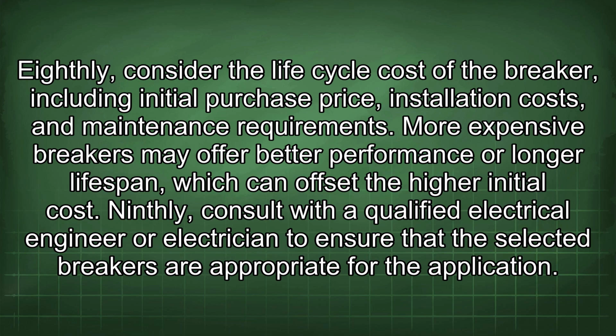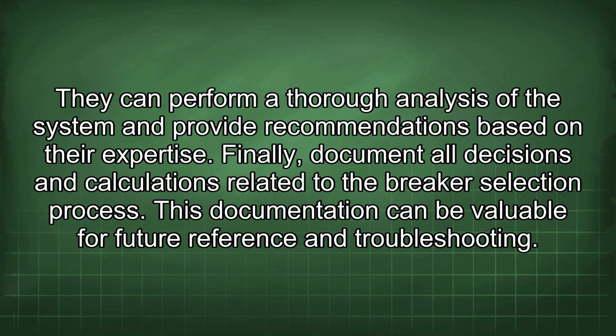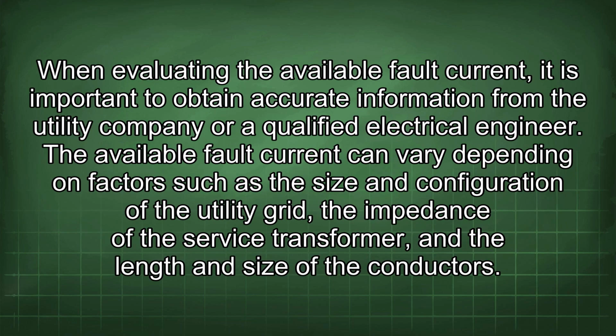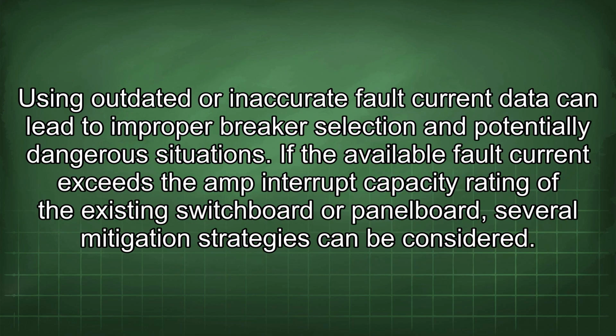Ninthly, consult with a qualified electrical engineer or electrician to ensure that the selected breakers are appropriate for the application. They can perform a thorough analysis of the system and provide recommendations based on their expertise. Finally, document all decisions and calculations related to the breaker selection process. This documentation can be valuable for future reference and troubleshooting. When evaluating the available fault current, it is important to obtain accurate information from the utility company or a qualified electrical engineer. The available fault current can vary depending on factors such as the size and configuration of the utility grid, the impedance of the service transformer, and the length and size of the conductors. Using outdated or inaccurate fault current data can lead to improper breaker selection and potentially dangerous situations.